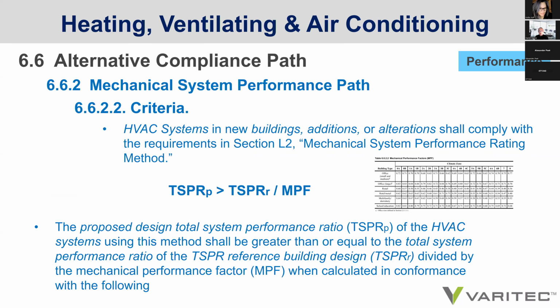The mechanical system performance path equation is shown below, where the total system performance ratio of the proposed building is greater than or equal to the total system performance ratio of a standard reference building divided by the mechanical performance factor as assigned by the table illustrated on the slide per the climate zone.